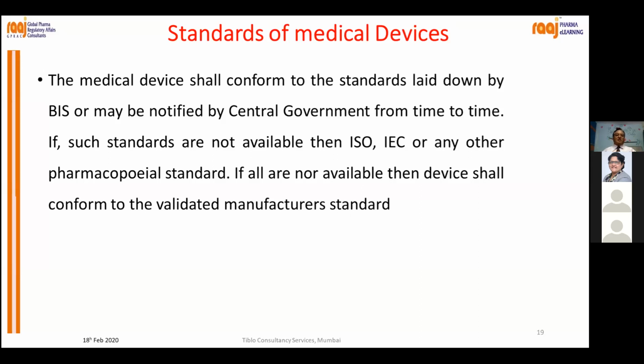A medical device must conform to the standards laid down by BIS. In India, if BIS has laid down a standard for a particular device, then your device has to conform to those standards, or any standard which has been notified by Government of India from time to time. And if Government of India or BIS has not notified any standard, then you can use ISO standards or IEC standard, whichever is applicable, or any other pharmacopoeia standard. If all the above are not available, then the device shall conform to the validated standards given by the manufacturer.